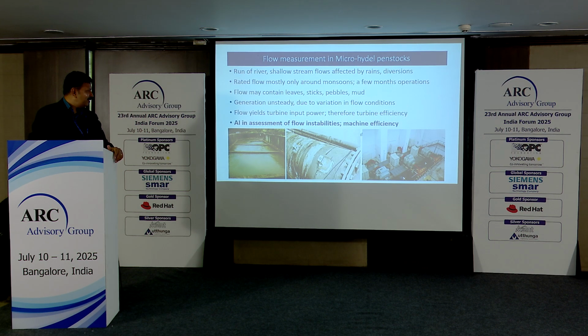Right. Now, in one particular case, on a run-of-river mini hydel power station in Hassan, we did an assessment where the discharge or flow takes place mostly during the monsoon. Maybe for 3 to 4 months you have good rains and good water, and after that it starts to go down. So the turbine or machine is not able to produce the rated outputs. The flow and the head are all varying, and by looking at the measurement you are uncertain whether the efficiency is drastically changing or not.